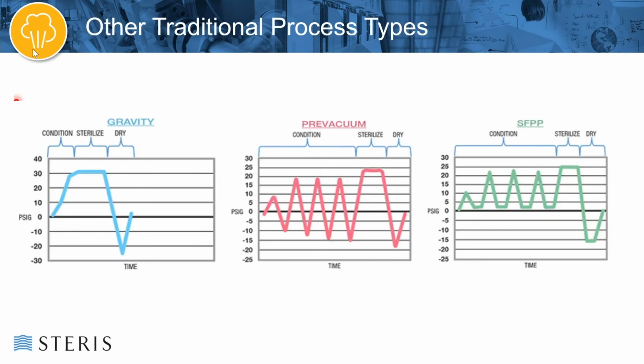We have what's called a gravity process and a pre-vacuum process, which we've already discussed, and we've also mentioned the SFPP, or the steam flush pressure pulse. With the gravity cycle, we start the cycle and chamber temperature and pressure rise, it plateaus, and then the steam is exhausted from the chamber. It comes down to atmospheric, where it draws a vacuum, enters a period of dry time, and then the air break back to atmospheric conditions. With the pre-vacuum cycle, again we have these pulses going up and down during the conditioning phase. In the sterilize phase, we charge, we plateau, and then we exhaust down to atmospheric, draw vacuum, do our dry time, and then air break back up to atmospheric conditions.